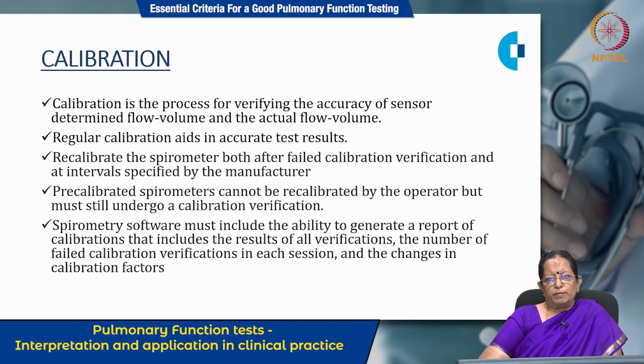Then coming to the calibration. This equipment should be calibrated. What is calibration? It is a process of verifying whether the accuracy of the sensor determined flow volume and the actual flow volume are almost equal. Regular calibration aids in accurate test results. You should recalibrate the spirometer whenever there is a failed calibration verification and also at intervals specified by the manufacturer.